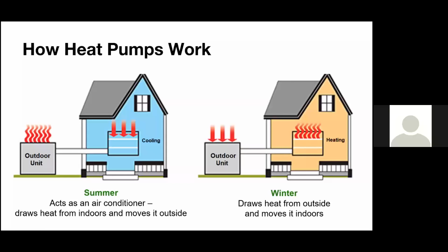Now, one of the things that happens when you compare these two scenarios is, on the left in the summer, just looking at the temperature differences, in your house you're trying to maintain, say, around 70 degrees in the summer. Outdoors, the worst case scenario might be 95 degrees in the New England climate. So there's about a 25-degree temperature difference that the compressor has to work against. So that's how much it has to compress the refrigerant in order to warm it up enough to be able to reject heat against that big temperature gradient.